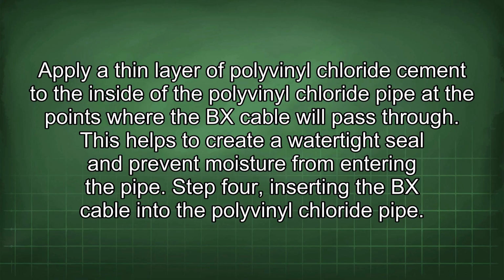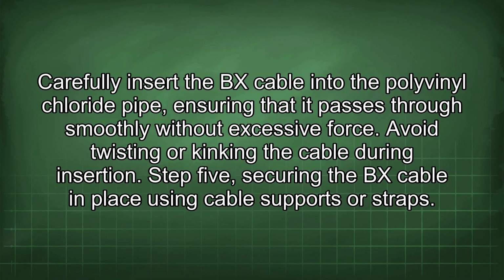Step 4. Inserting the BX cable into the polyvinyl chloride pipe. Carefully insert the BX cable into the polyvinyl chloride pipe, ensuring that it passes through smoothly without excessive force. Avoid twisting or kinking the cable during insertion.